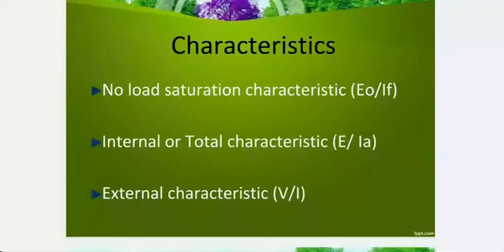You will see that initially E naught, the no-load voltage coming out, will rise linearly with the field current. But after a certain value is reached, you will start seeing saturation coming in, and then E naught will flatten out no matter how high an IF you try to put in. In fact, the wires may even break down if you put too high a value of IF.